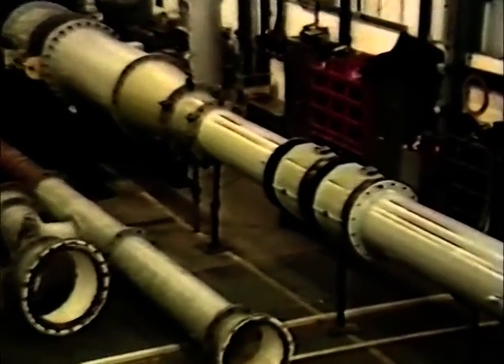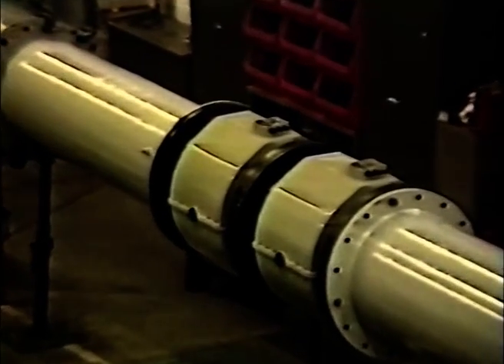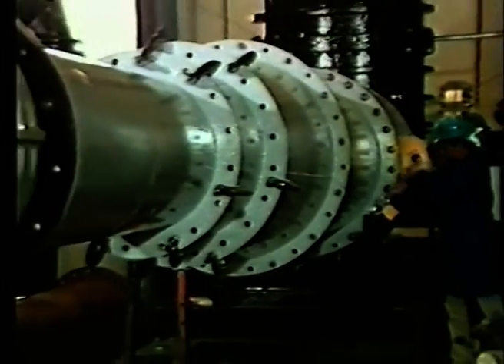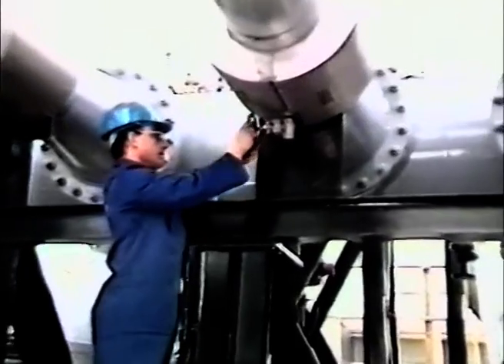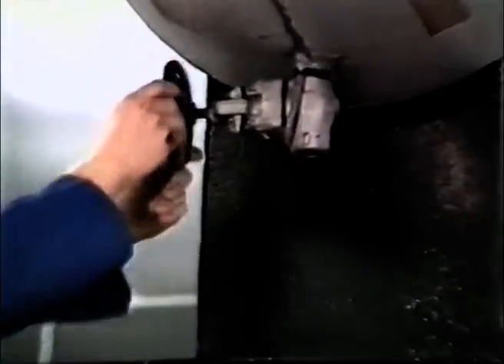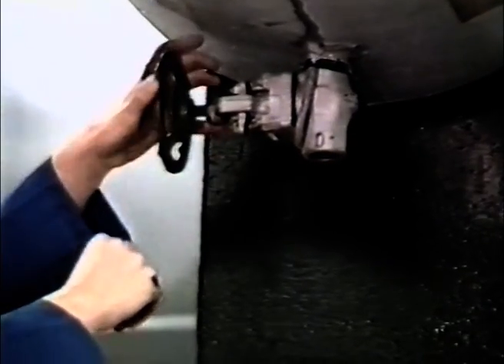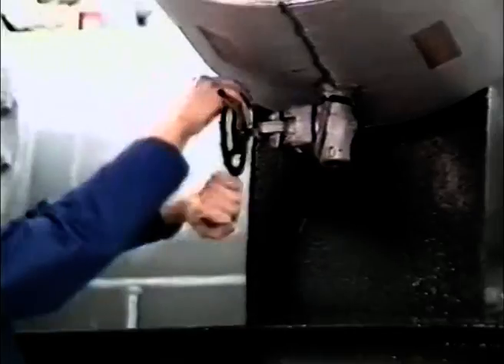And depending upon the size of the meter under test, you can connect it into a line directly or via a system of concentric cone pieces. In fact, you can fit, test and remove meters on different lines at the same time, which is a great aid both in efficiency and flexibility. The plant can accommodate any meter size, from 300 millimeters right up to 2 meters. Obviously, the same holds true for control valves. And speaking of control valves, it's worth noting here that the valves controlling this plant are all high-integrity block and bleed types to ensure 100% accuracy of flow diversion around the rig and prover system.